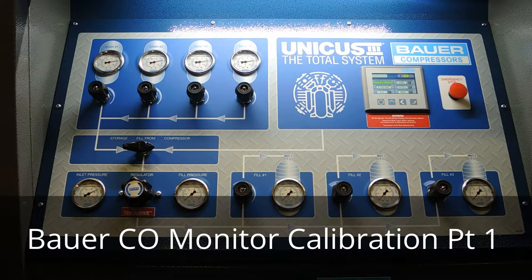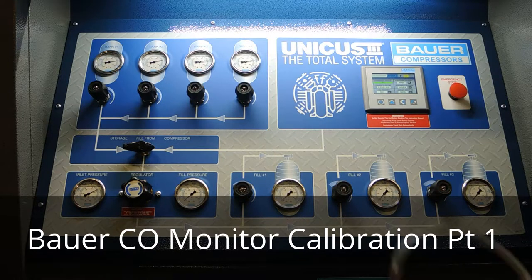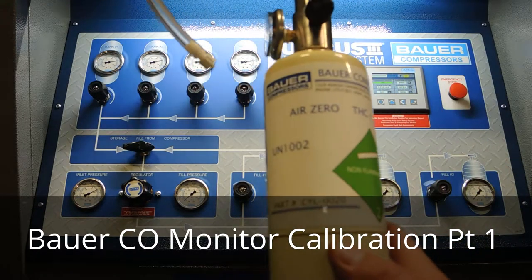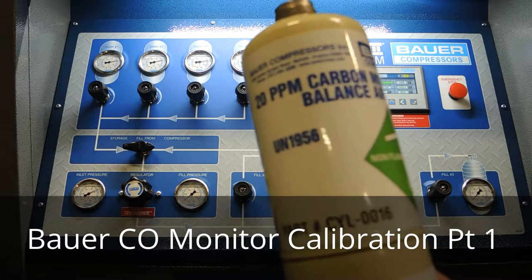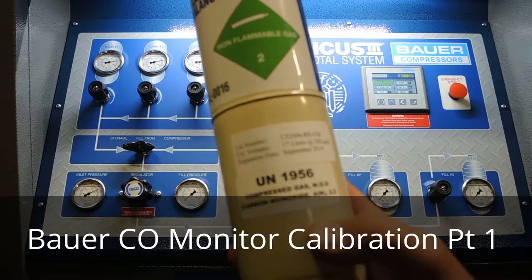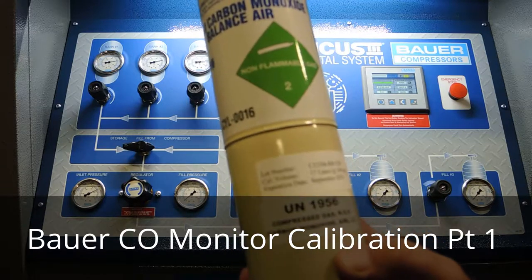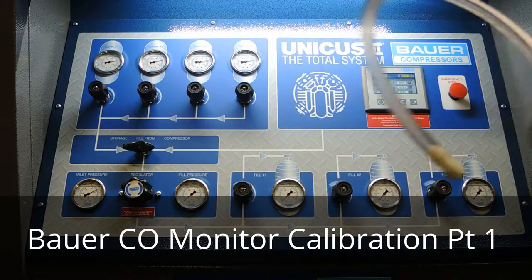There's going to be a couple of things that you need to make sure that you've got. You want to make sure you have your test gases. There's going to be two test gases required. You're going to need your zero gas and also your 20 part per million test gas. Make sure that these are not expired and that there is a proper range of gases.